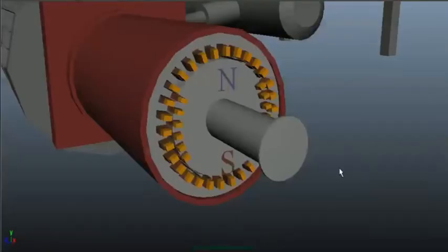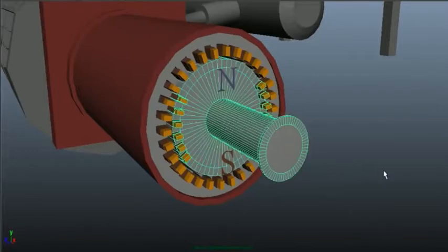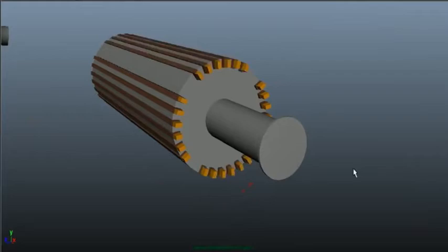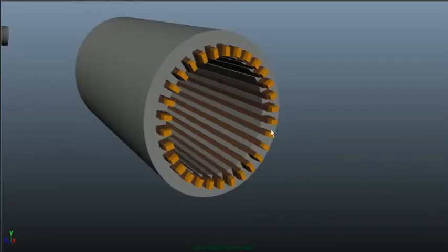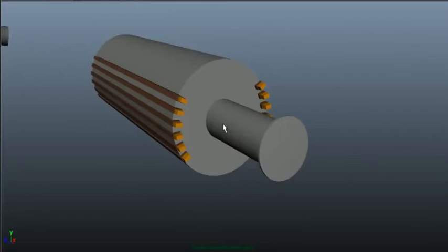These high-speed generators are also known as turbo alternators, and their rotor can only be designed for 2 poles or 4 poles. Because if we design its rotor for a higher number of poles, then its stator winding requires large space for the three-phase winding. So ultimately the diameter has to be increased, which is not possible for high-speed machines. Now we know the work of the rotor is to create magnetic poles, that is, north at one side and south at another, and it rotates along with these poles. So to create fixed poles, the rotor winding requires a DC supply.